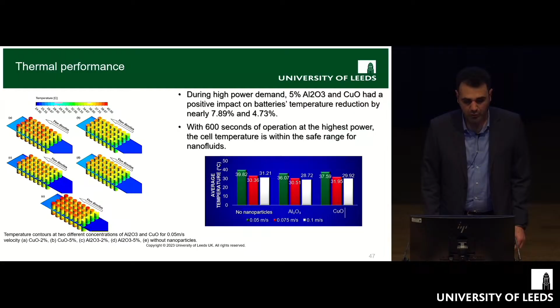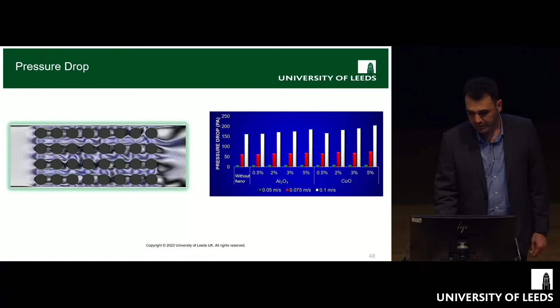So that was the analysis we also did for pressure drop. At low velocity, for 0.5% and 2% concentration, the pressure drop was not quite significant, about 1 to 5%, but when we increase to 5%, the pressure drop changes between 8 to 12%, which becomes quite significant as well.